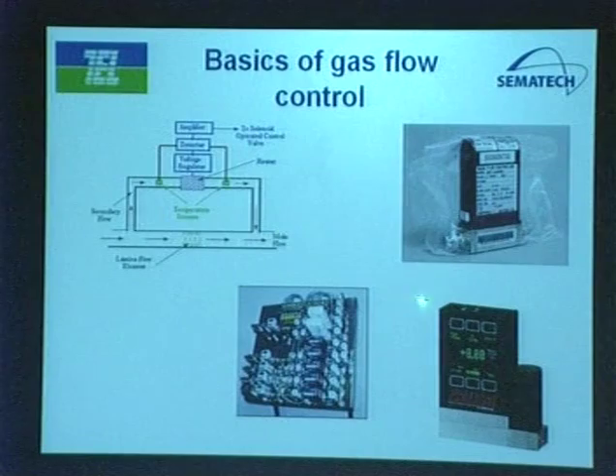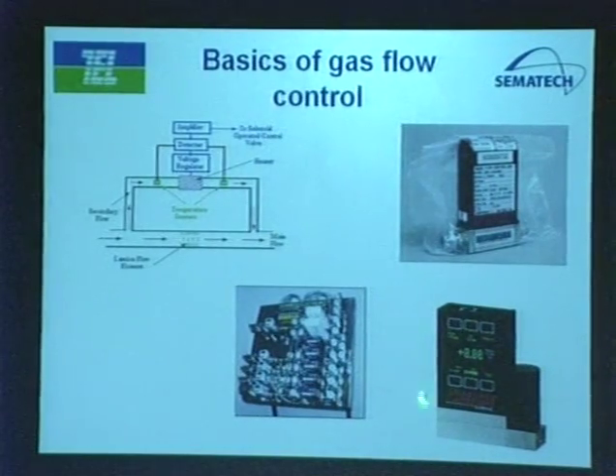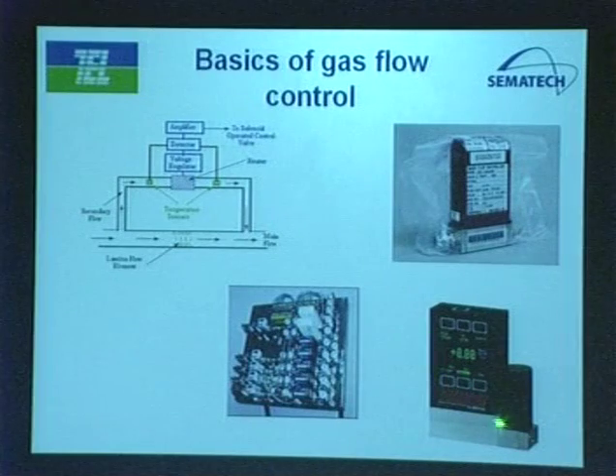Basic gas delivery systems are controlled by units that look like this on the tool. This is a surface mount system you can plug and play out of a gas panel. A gas panel looks something like this, where we have MFCs, mass flow controllers, many of them mounted. It's a really complex system with gas valves on both sides of the MFC, and ways to purge these MFCs to keep them clean so they function as expected.